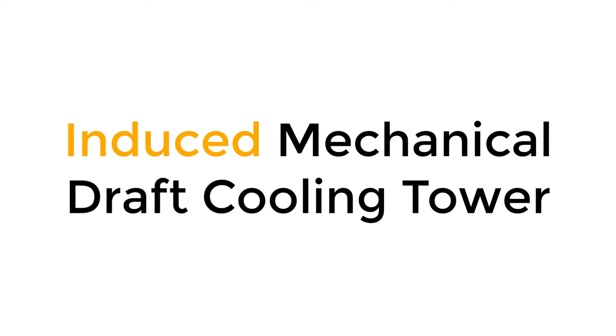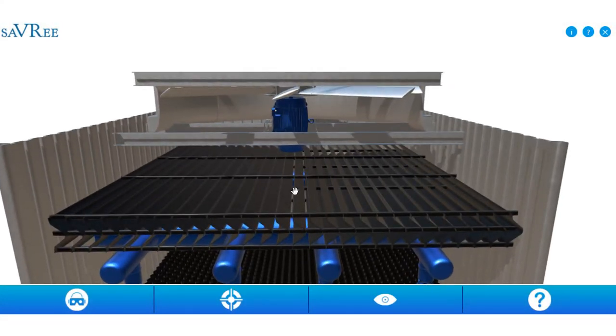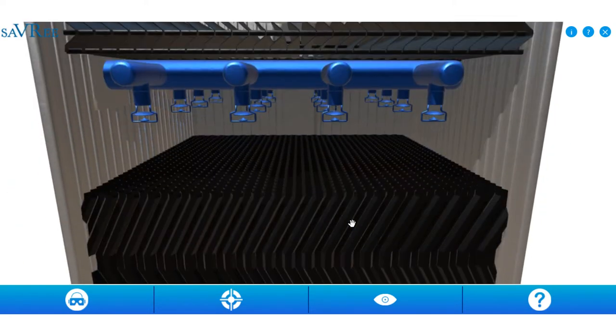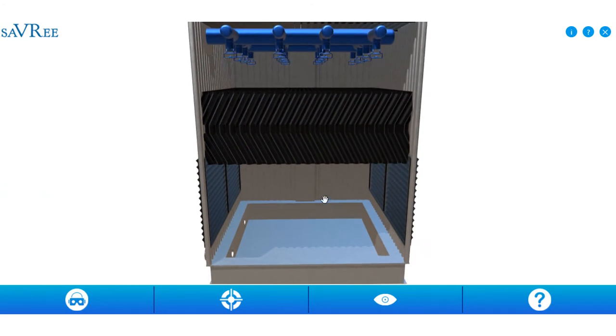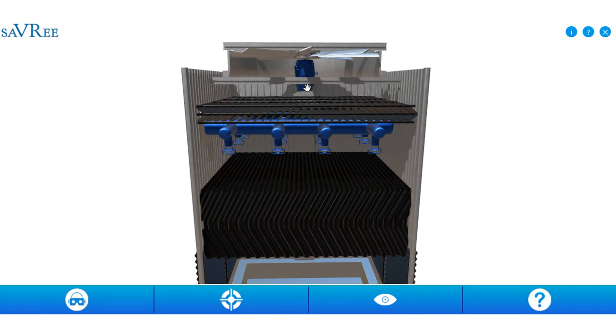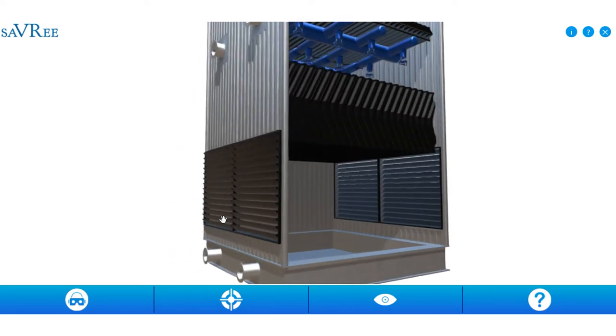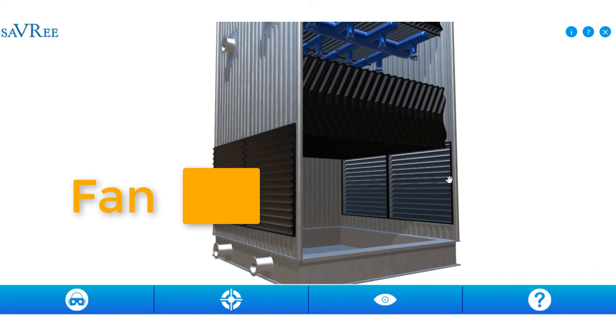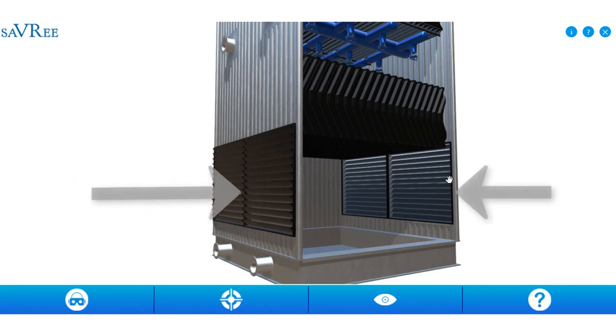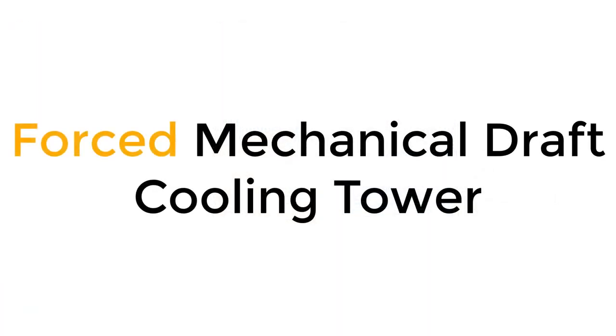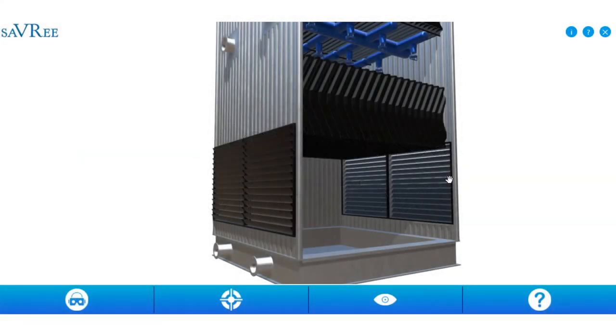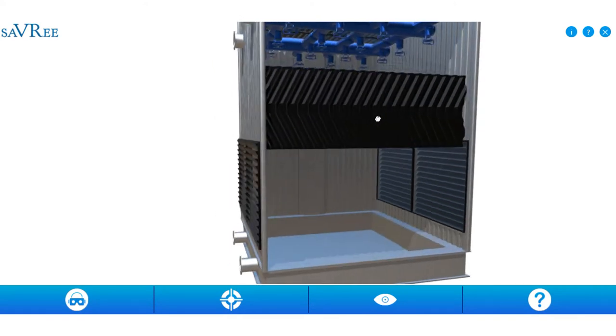When we say induced, we mean we're inducing a movement of air on the back side of the fan, creating a negative pressure within the cooling tower. The air is drawn up through the bottom, through these grooves, up through the heat exchanger, through the nozzles, through the drift eliminator, and out the top. If the fan were at the bottom, blowing air in, that would be forced draft. Forced draft means you're forcing air across the heat exchanger; induced draft means you're drawing air in across the heat exchanger and expelling it outwards.